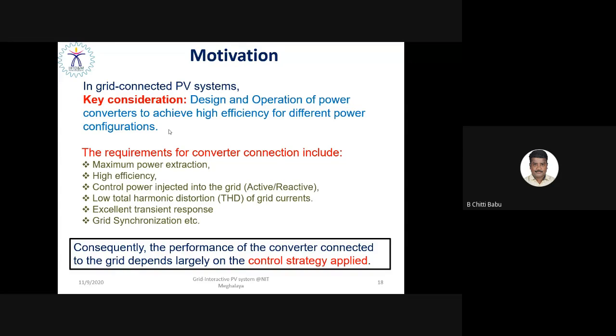So the performance of such a converter connected to the grid largely depends on the control strategy being applied, because you are trying to inject controllable active as well as reactive power into the utility grid. How the control requirements are going to be met purely depends on the control technique employed on the grid interactive power converter, right? So how the control strategy satisfies the above set requirements, that is a very important motivation.